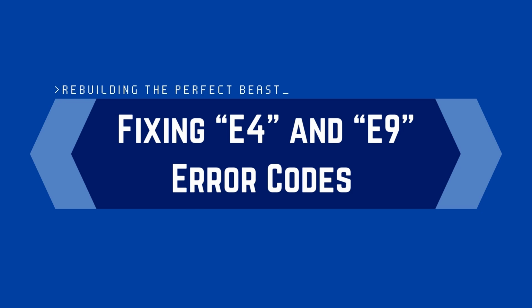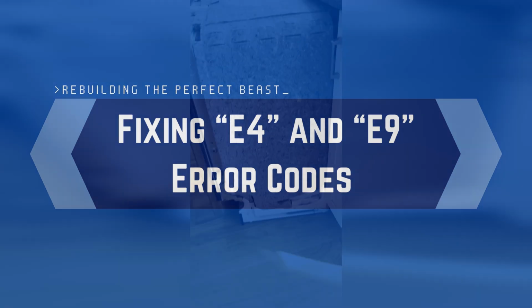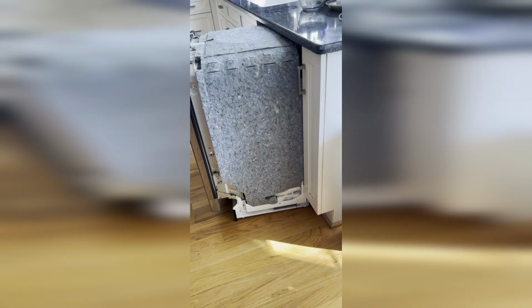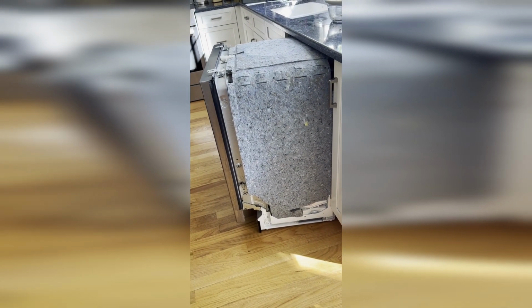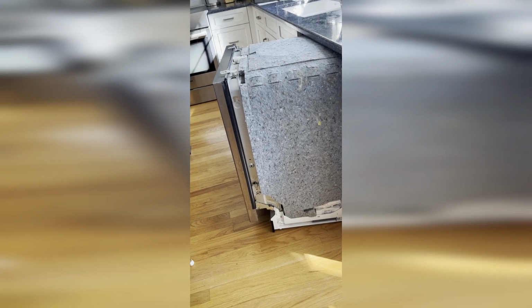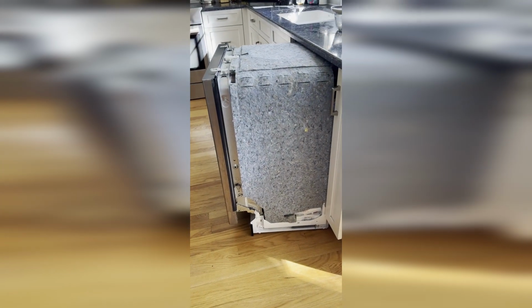So that's the E15 error and how to deal with it in the short term if you want to keep it going. I'm going to talk about the other error code this machine had, which was first an E4 and then an E9. The E4 is a thermal code where it's not coming up to temperature. It's getting there, but it's not there yet. So you'll see it looks like it's working and it's hot, but it'll say E4.